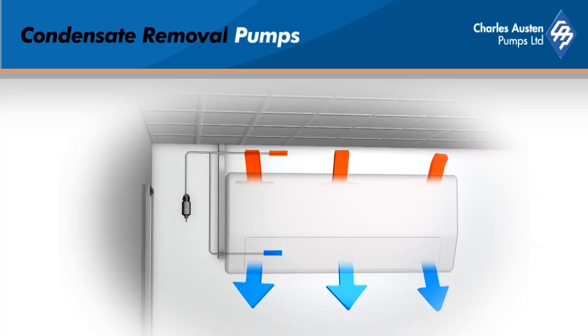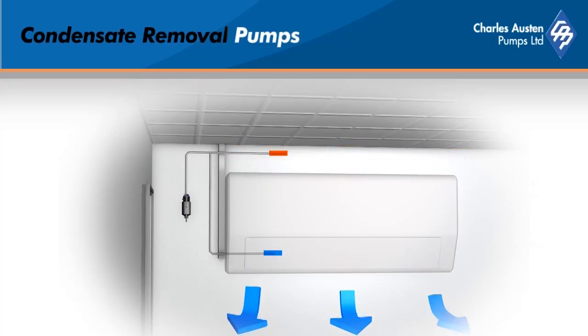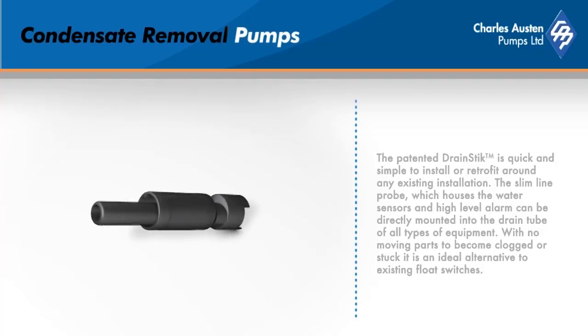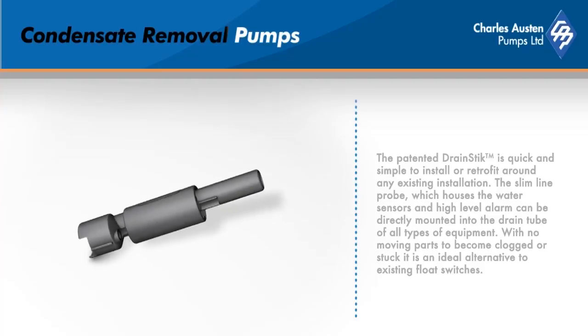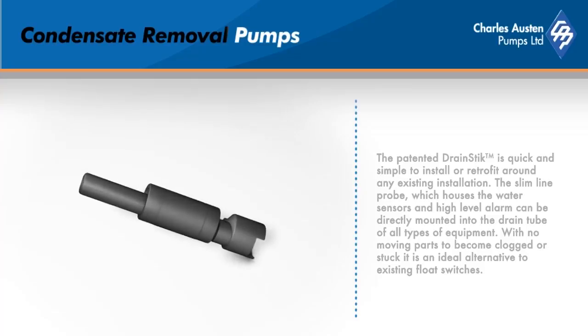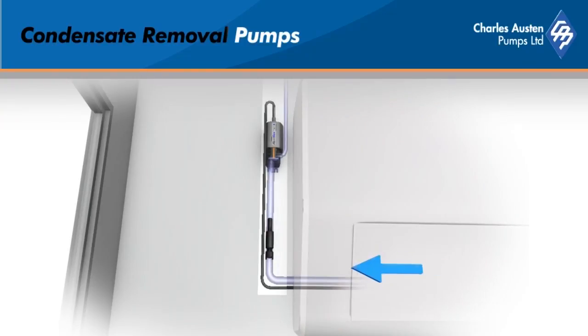A universal stepped adapter is supplied with each pump, specifically designed to connect any drain pipe to the Blue Diamond range. The patented DrainStik optional accessory is quick and simple to install or to retrofit around any installation. The slimline probe houses the water sensors and a high-level alarm. The DrainStik can be directly mounted into the drain tube of all types of equipment. With no moving parts to become clogged or stuck, it's an ideal alternative to existing float switches.